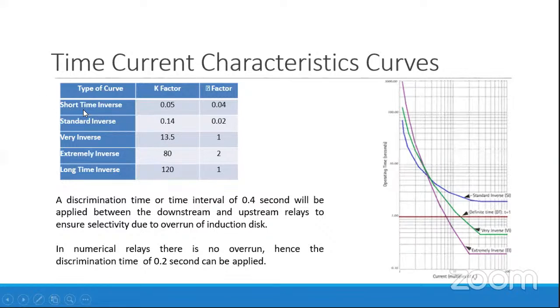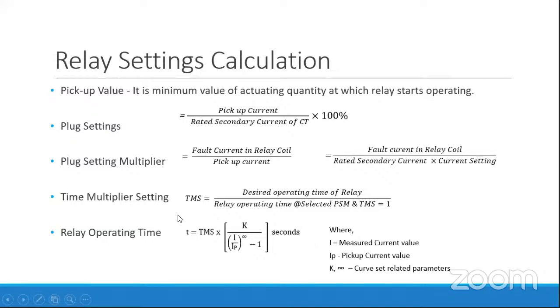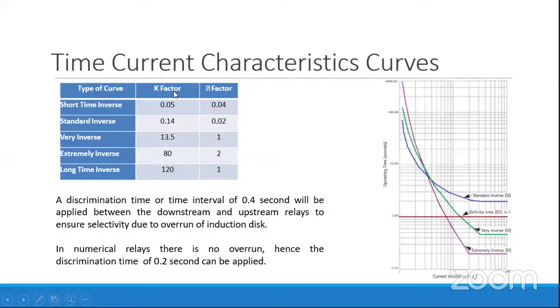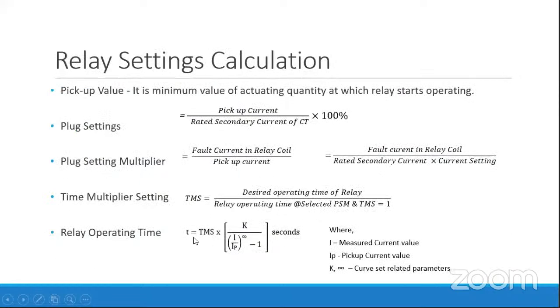For the short time inverse curve, the K parameter is 0.05 and infinity is 0.04. The question mark here is infinity. For the standard inverse, it is 0.14 and 0.02 for infinity. These values should be placed in this equation, that is K. Let's take the example of standard inverse: K is 0.14 and infinity is 0.02, and these should be put in this equation. Then with the measured current value and the pickup value at which we want the relay to operate, we can get the relay operation time.